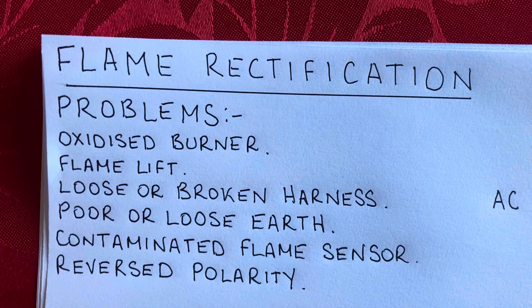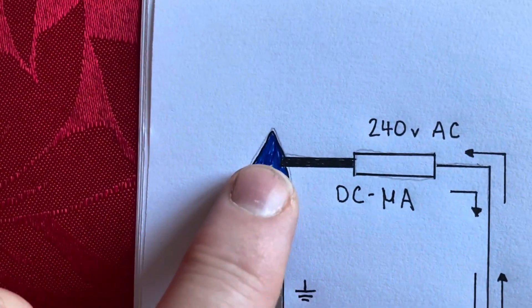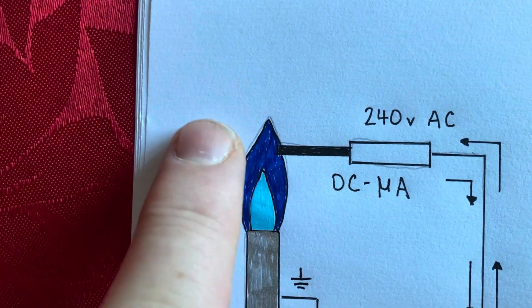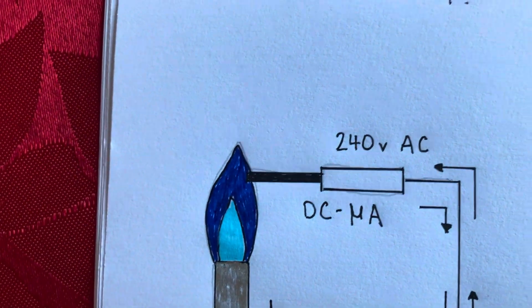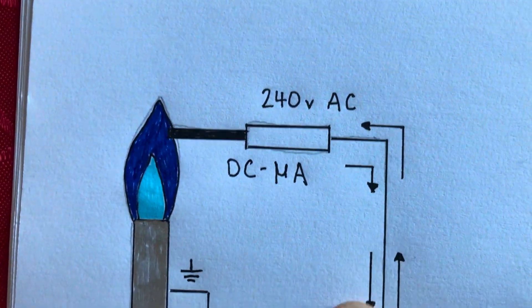The first problem is an oxidized burner — basically a rusty burner — where you're not getting a good earth connection. That's one to look out for. The second is flame lift: the flame isn't touching the probe properly, possibly due to poor oxygen supply into the boiler or a problem with the flue, which can lift the flame away from the probe.